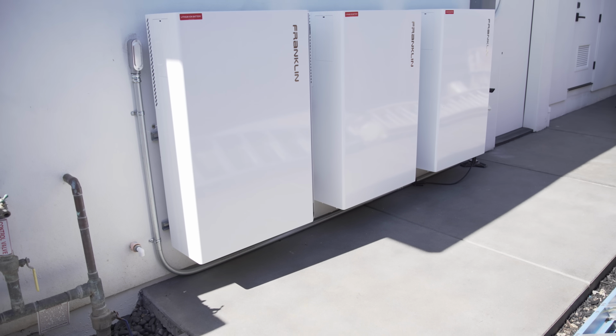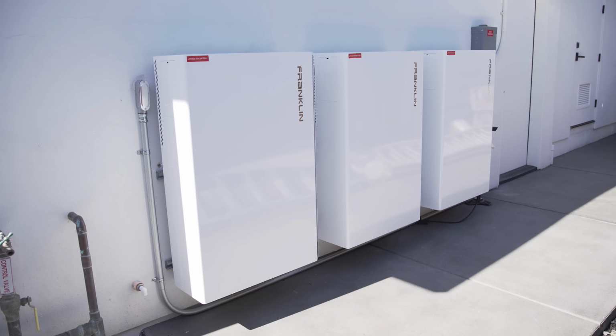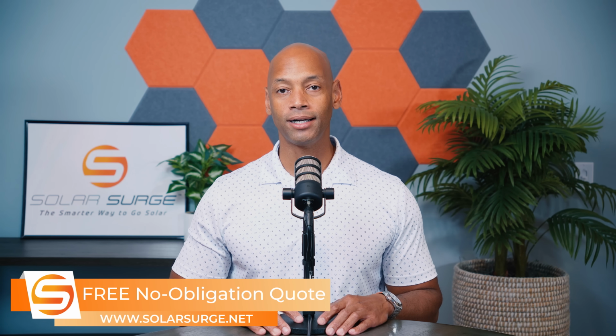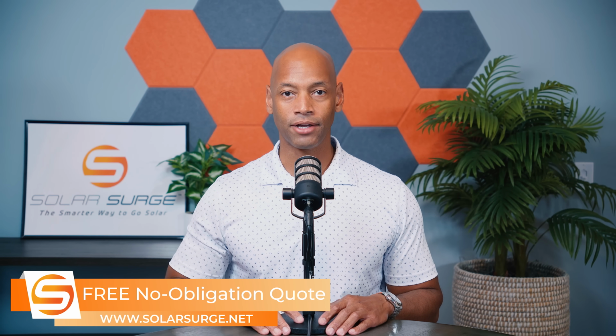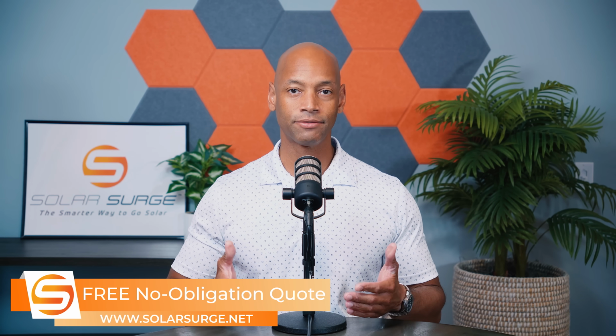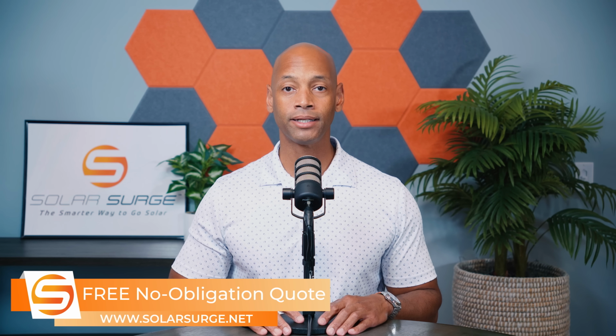In the past we may have just called it a transfer switch. If you're familiar with whole house generators, typically you have a transfer switch, or ATS, automatic transfer switch, which allows the home to disconnect from the utility but still allow the generator to energize the house. With a solar battery backup system you need something to do that same function, and we typically would call it a gateway, system controller, or hub. All the manufacturers call it something different, but basically it's the transfer switch - the way you switch off from the grid and still energize secure power in the house.